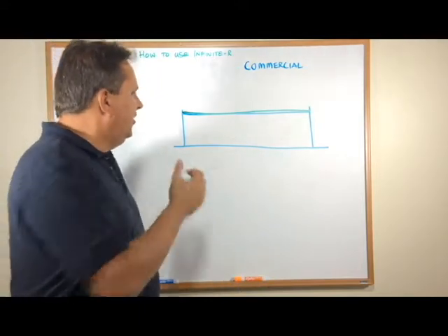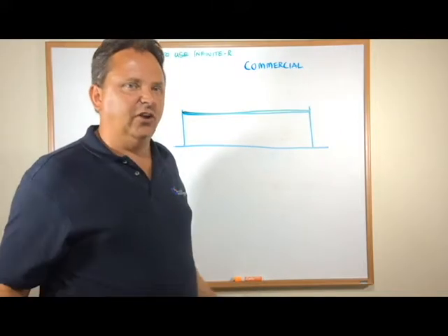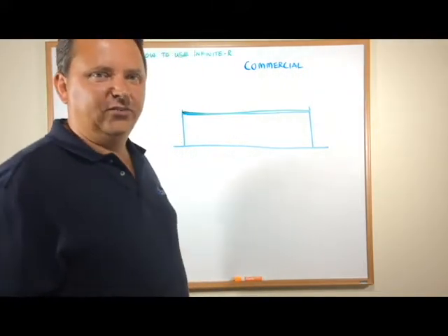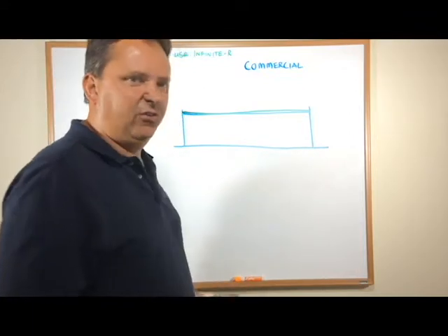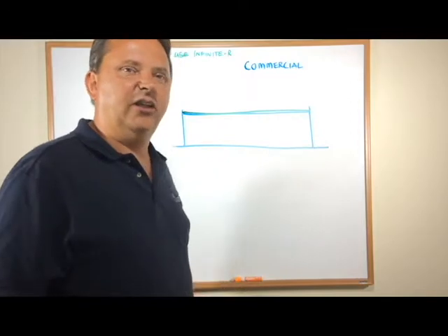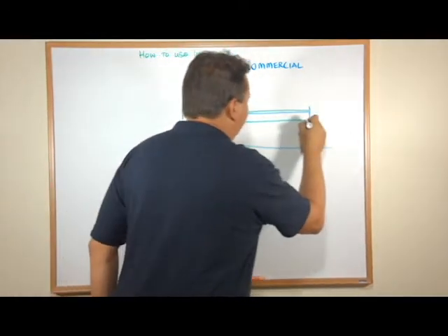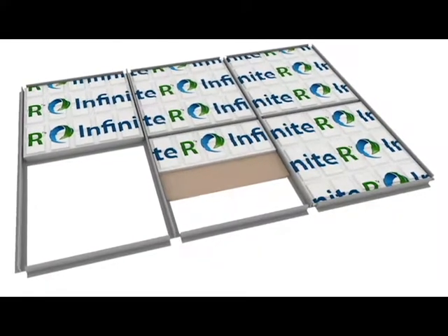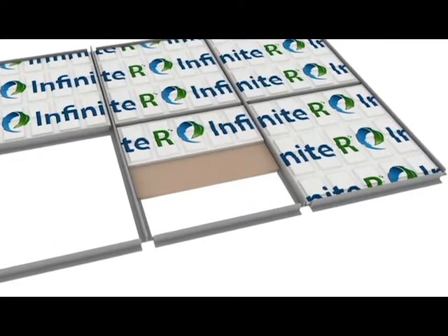Because large retail stores have so much roof area, this is always the first area that you want to look at. Now there's a second way to do buildings if you can't get access to the roof. Say you're retrofitting, or there's something in the roof sector that doesn't allow you to have phase change. Another option we have is to put the phase change over the ceiling tiles. So we basically pop up the ceiling tile, lay a bunch of phase change around it, move on down 10 feet and do so again.